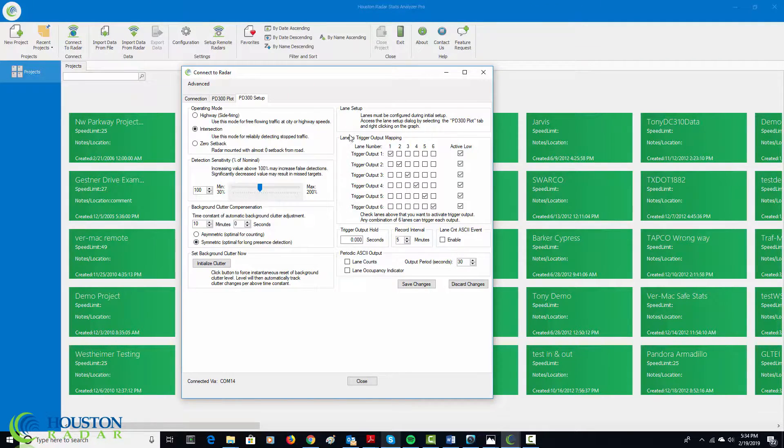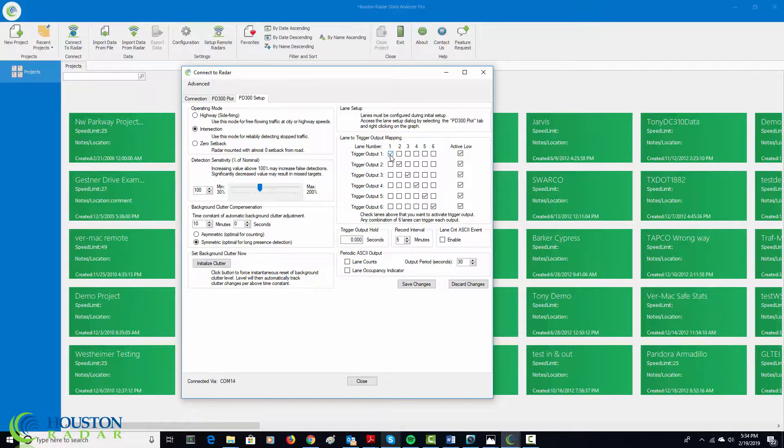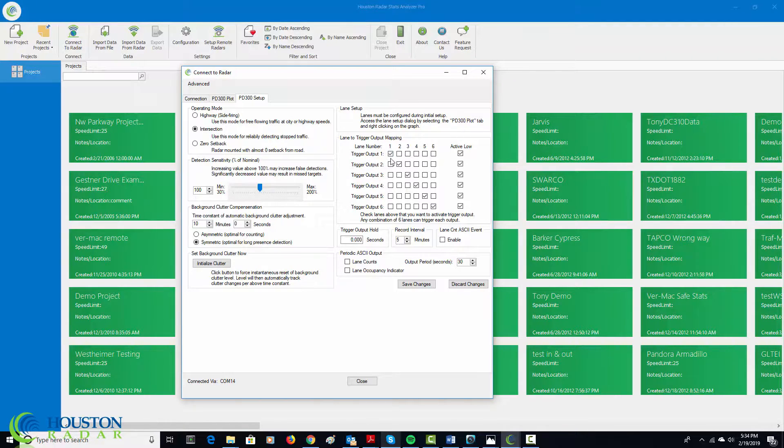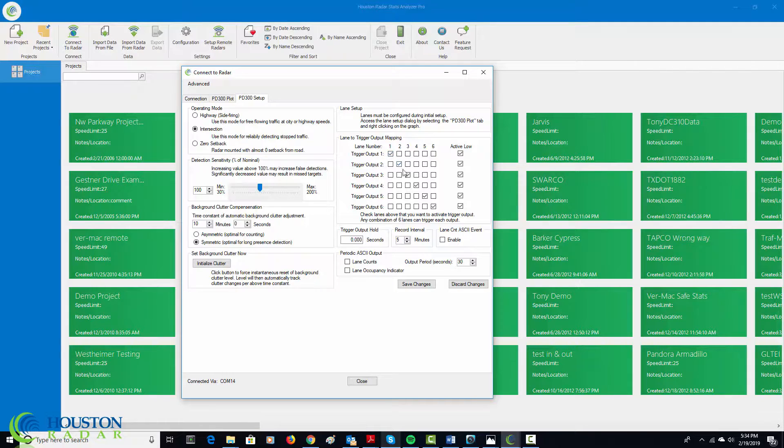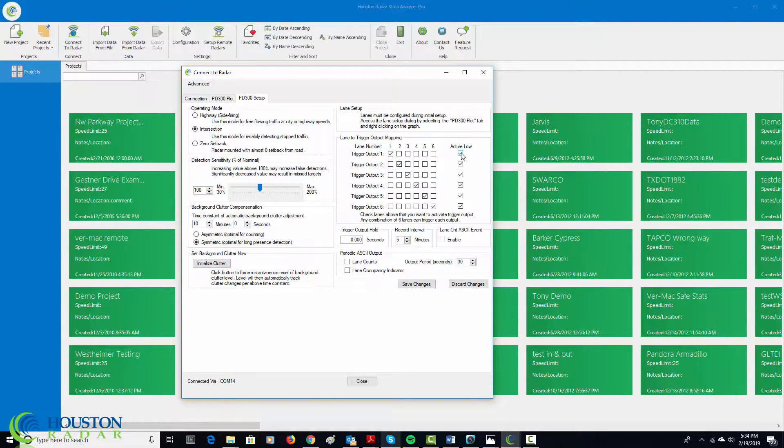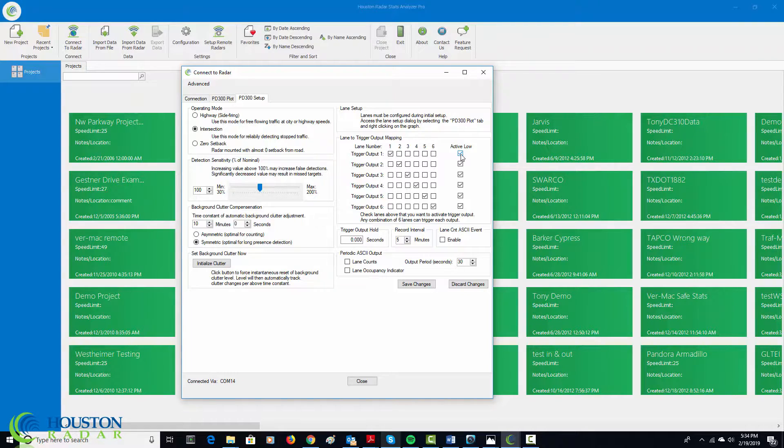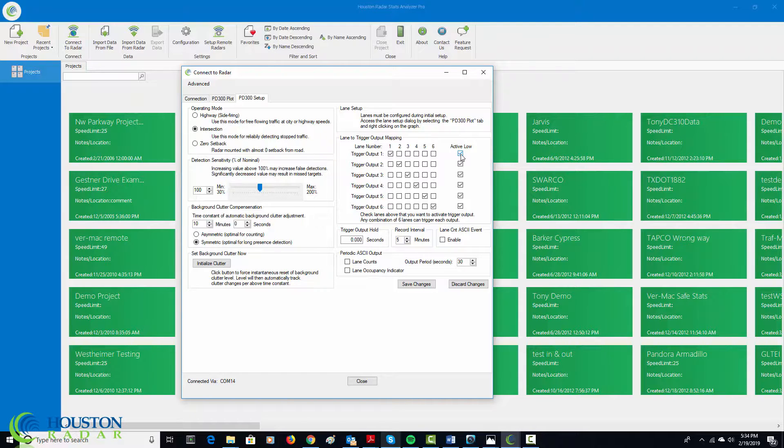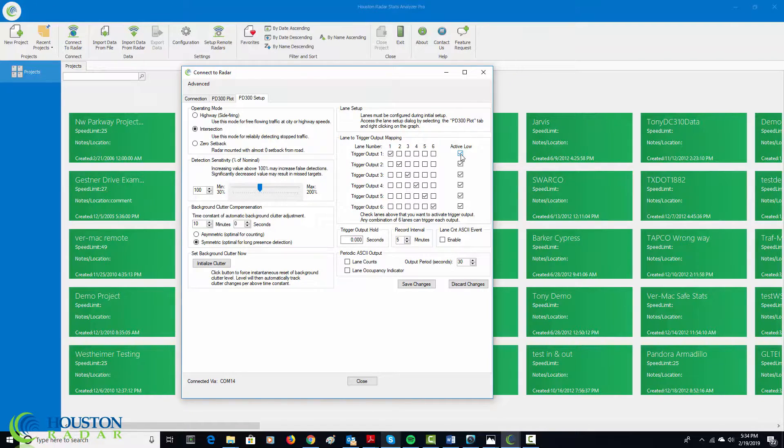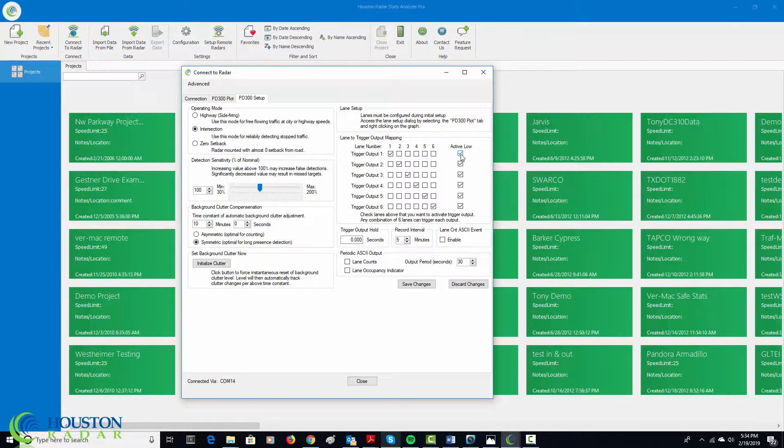Let's move on over to the triggering. So today, we are just going to have one lamp set to trigger 1 output, in which case I will say the trigger 1 should be triggered by lane 1 and I will demonstrate that. And then you can just ignore the other outputs. Since the lamp is going to be turned on when the output goes low, we want an active low, which means when a target is detected in the lane, the output will be pulled low, and then the current will go through the lamp and activate the lamp. You can also select the trigger output to be active high, in which case the output will be released, and then you need to provide a 5 or a 10 kilo-ohm pull-up resistor for the output to be pulled high. This typically would be if you are going into a PLC or a DCS where you require a high-going output on detection.